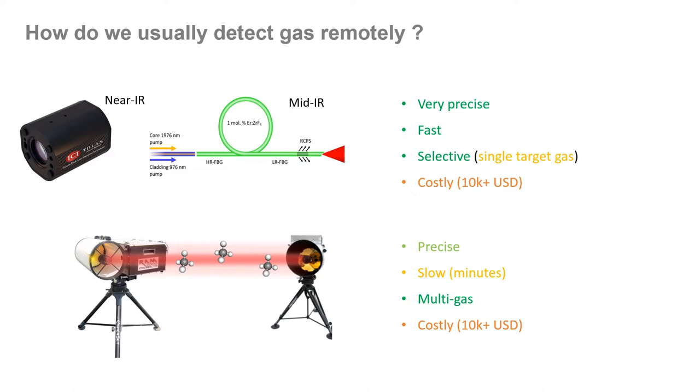In the case where multi-gas detection is desirable or when the target gas is unknown, the absorption spectral measurement is preferred. Unfortunately, the measurements can take several minutes and they are a little less precise than what you can get with the tunable laser approach. This is mostly related to the time needed for the spectral measurement and data processing. And again, these systems can be quite expensive because of the need for a spectrograph or monochromator, for instance.